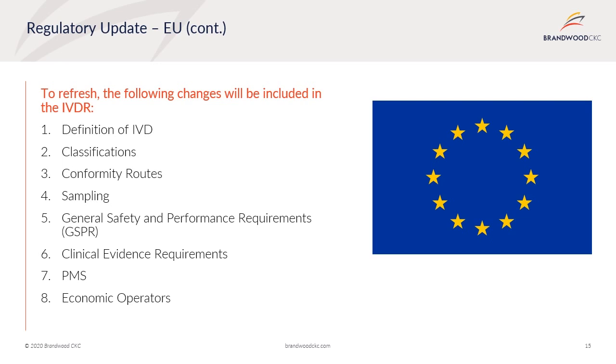The clinical evidence requirements in IVDs, this is a huge change because there wasn't an expectation that clinical evidence would be talked about in such a manner. But in the performance evaluation report, there is an expectation that clinical evidence is addressed. And again, it's not to suggest that every client in the world has to go out and do clinical evidence on their IVDs, but it is to suggest that you have to have substantiation as to the evidence that you have on file for the clinical efficacy.